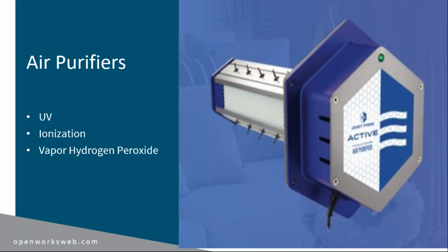The last technology is vapor hydrogen peroxide, also called photocatalytic oxidation. This is achieved by shining a UV light on a cell that acts as a catalyst. The process produces an off-gassing of vapor hydrogen peroxide that will get distributed through the supply air ducting of the building. This vapor hydrogen peroxide cannot be seen, however, it is landing on surfaces and disinfecting wherever it lands.